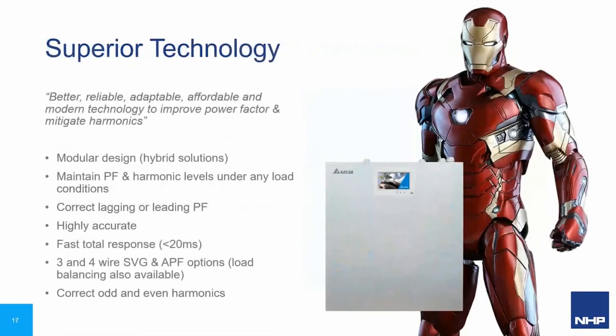So let's talk about the superior technology of SVG and APF compared to other power quality methods. It's that modular design again that I mentioned before that allows you to make hybrid systems, so you can have SVG and APF modules in a single cabinet, effectively providing all levels of power quality. So under any load conditions, you're maintaining your power factor and your harmonic levels. Again, it corrects both lagging or leading power factor and does load balancing. It's that fast response time. And it can correct both odd and even harmonics, specifically for the APF.